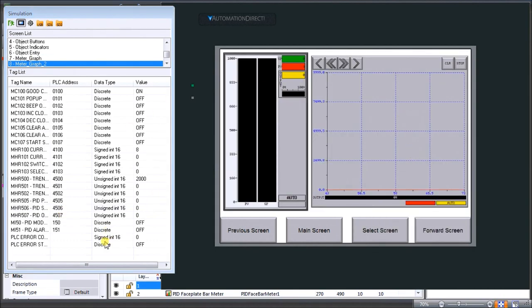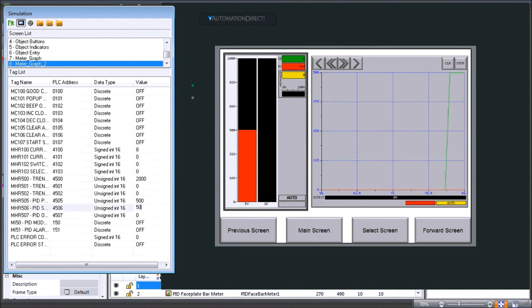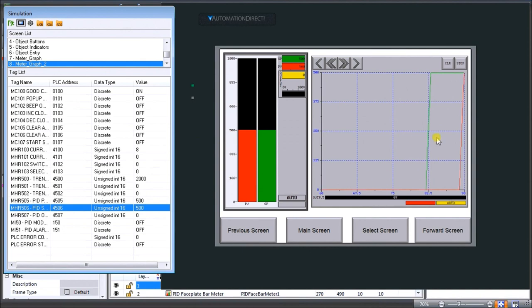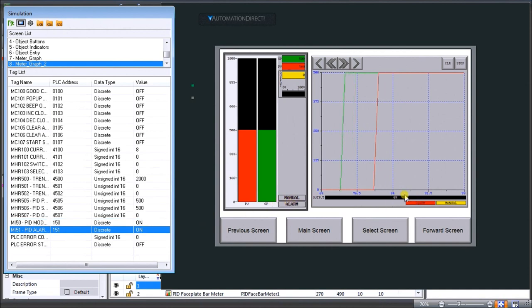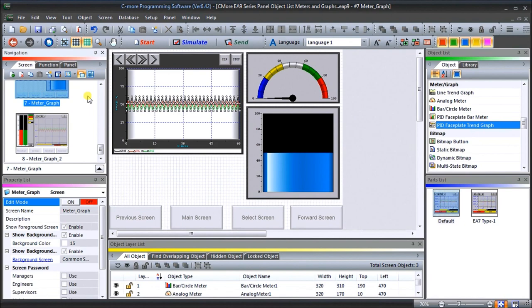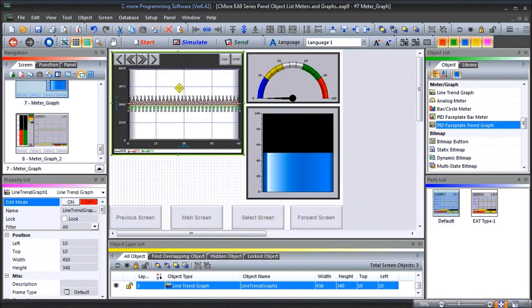We'll select our screen and go to meter graph two. Under the trends we can try 500 — that looks good. We see all values set at 500, 500. We can turn on our alarm — you'll see 'manual' here, and turning on the alarm shows the alarm indicator, which looks like it's functioning correctly. Let's exit and go back to our trend graph. We'll change the scaling from 0 to 4095, hit OK, and the scale is now correct. That's a good way to use simulation before transferring to the actual unit.